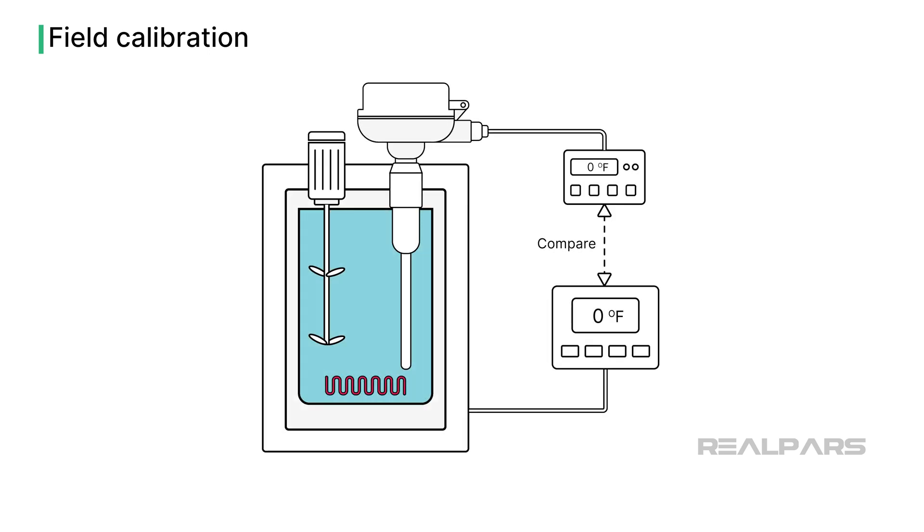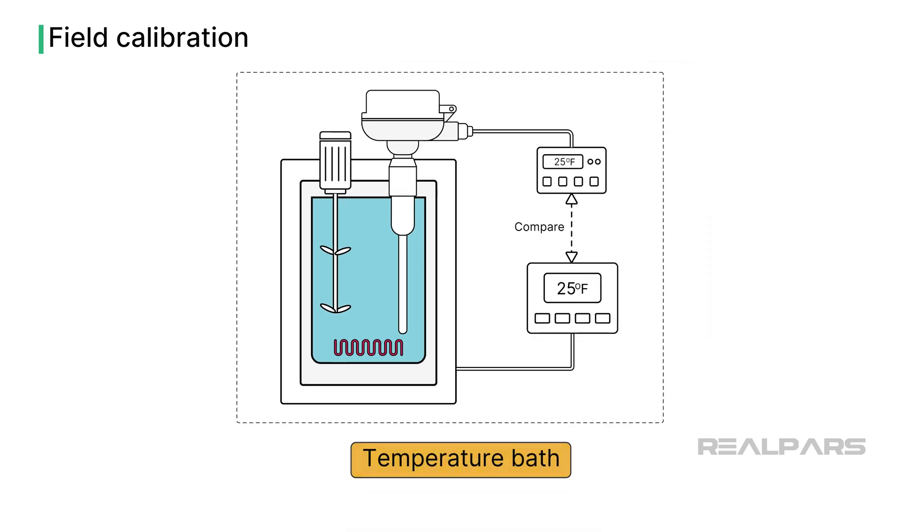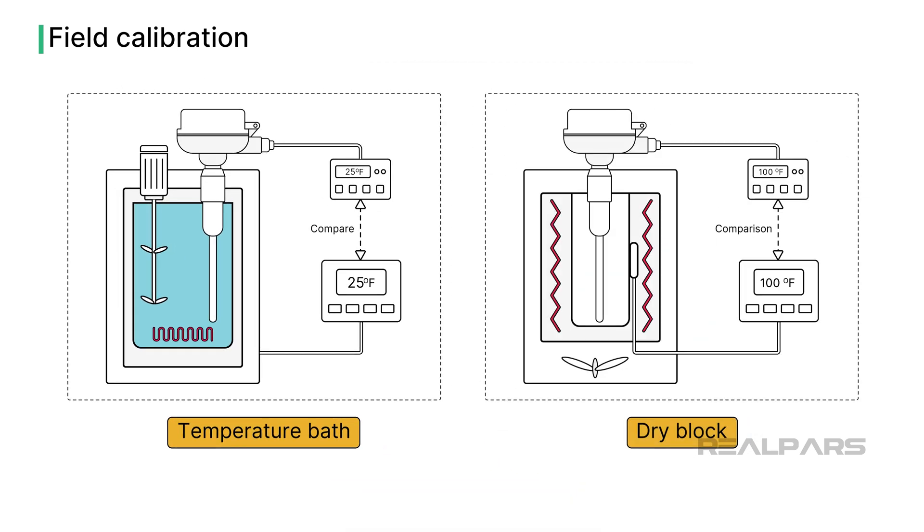Calibrating an RTD involves comparing its resistance output to a known temperature standard using a temperature bath or a dry block calibrator, providing precise temperature conditions.